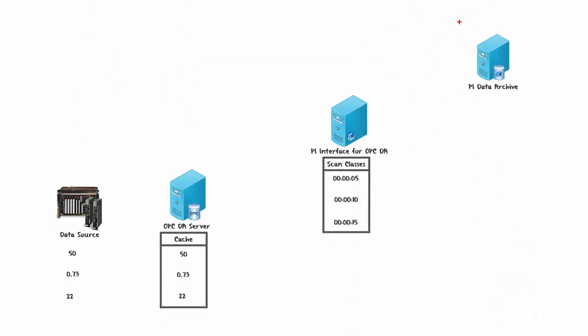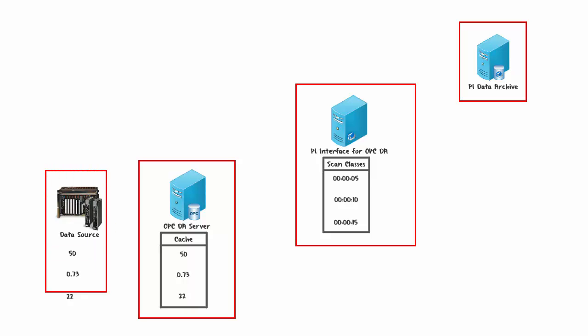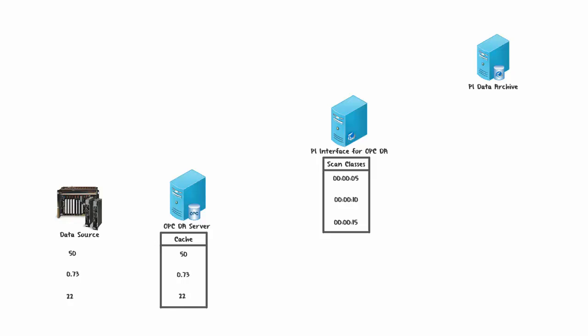Here we have a PI Data Archive, a PI Interface for OPC DA, an OPC Server, and a Data Source. One important concept is the OPC Server Cache — basically a table that the OPC Server keeps with the most recent values obtained from the Data Source. When the PI Interface for OPC DA starts, it scans the PI Data Archive for PI Points belonging to its different Scan Classes, which are turned into OPC Groups, and makes requests to the OPC Server for those groups.